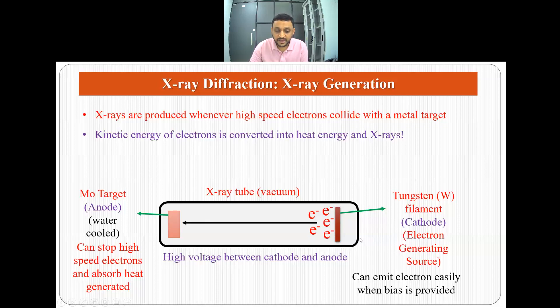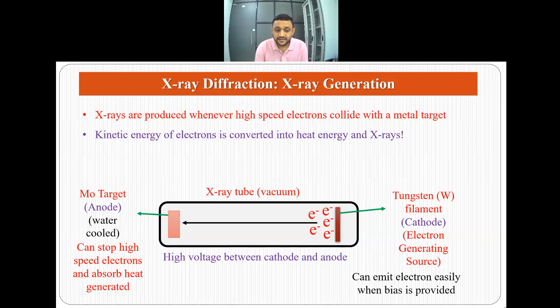In an X-ray tube we have a tungsten filament which is the cathode and our electron-generating source. We have a high voltage between cathode and anode, and the X-ray tube is in vacuum. The electrons move rapidly from the tungsten filament toward the metal target anode, striking it, and the kinetic energy is converted into heat energy and X-rays. A refractory metal is used as the target because it can stop high-speed electrons and absorb the heat generated.